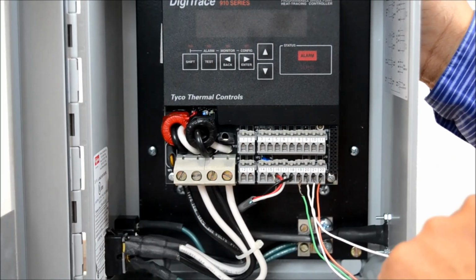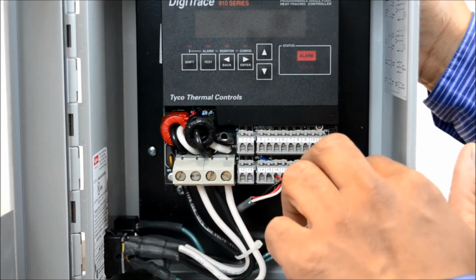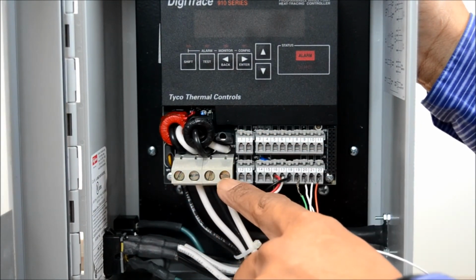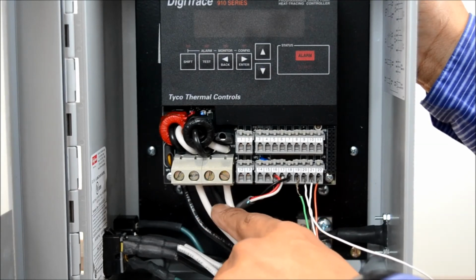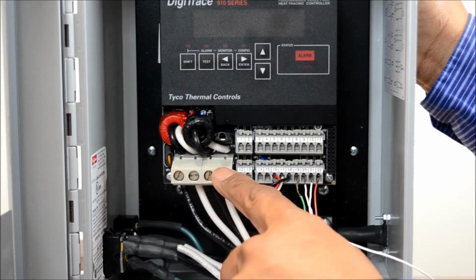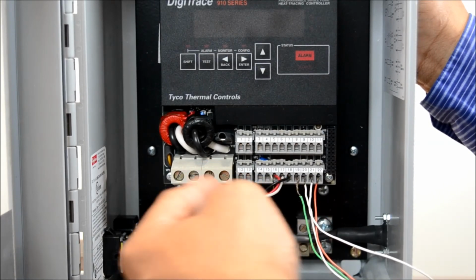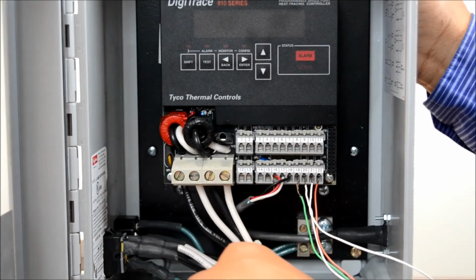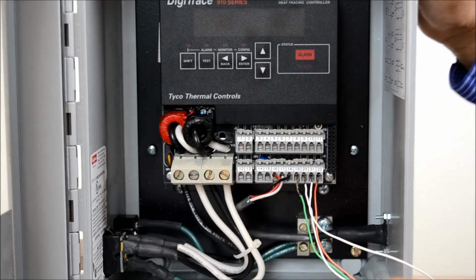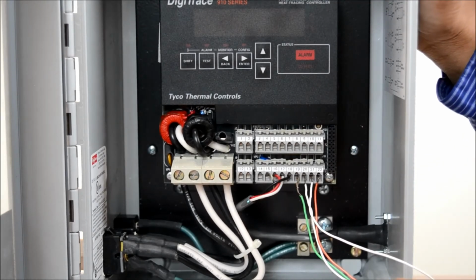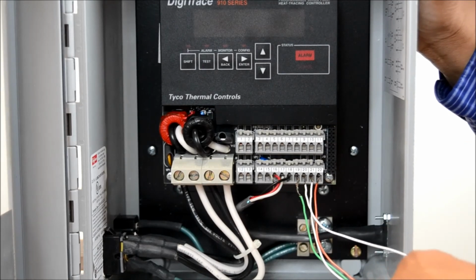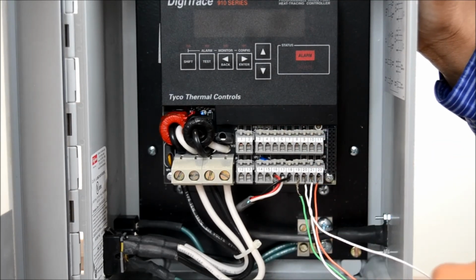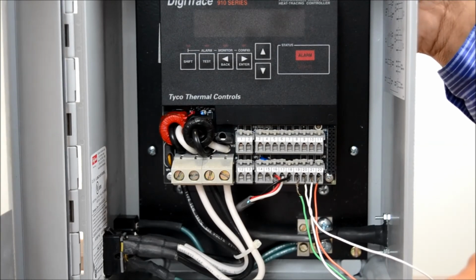As you can see inside the controller, these components are all low voltage, so it's not really a big hazard for shock here. The only hazard for shock would be these terminals here, which are the line voltage and the output voltage. And the only way you would really be able to get to those is if you actually stuck something inside those terminals. Of course, I mentioned many times before, this also has a safety mechanism as far as ground fault protection, and this is equipment protection ground fault. And this enclosure is rated for a Class 1 Div 2 area as well. And pretty much that's all the safety features this unit has.